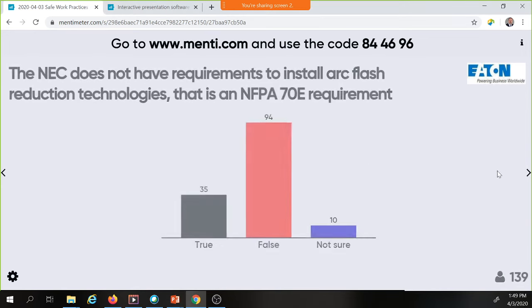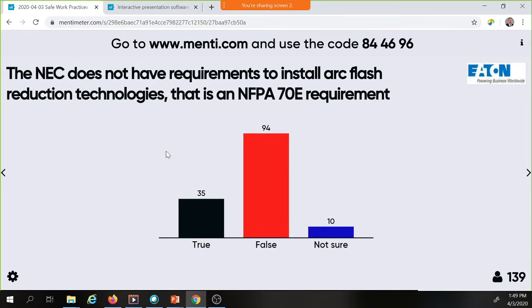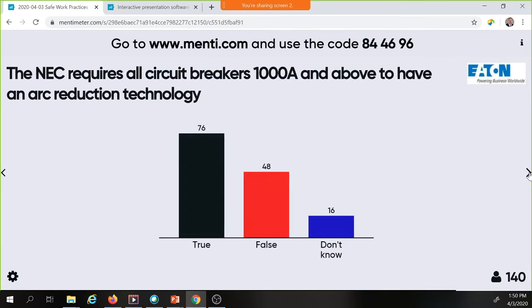Take a look at the next question. The National Electrical Code does not have requirements to install arc flash reduction technologies. That is an NFPA 70E requirement. That is false. It does have, and I went over those earlier, I believe, throughout the week. I've mentioned 240.87 and 240.67. Those are both areas where the National Electrical Code includes requirements to reduce incident energy. And so the 35 of you, you need to do your homework. Look at 240.67 and 240.87 in the National Electrical Code.